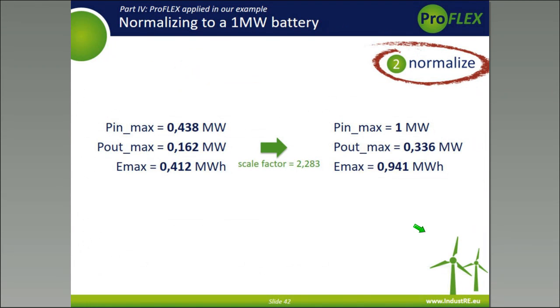Now, what is the trick? The first trick is we normalize everything to a 1 megawatt equivalent. By applying a scale factor of 2.28 on the original numbers identified in the previous plot, we get: 1 megawatt input power into the battery, an output power of 0.3 megawatts, and a virtual battery size of about 1 megawatt hour.